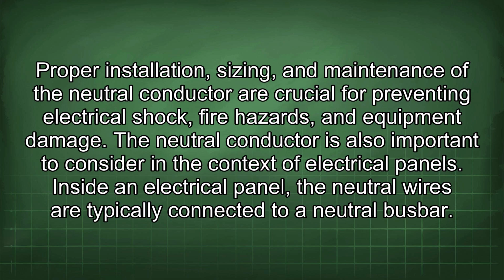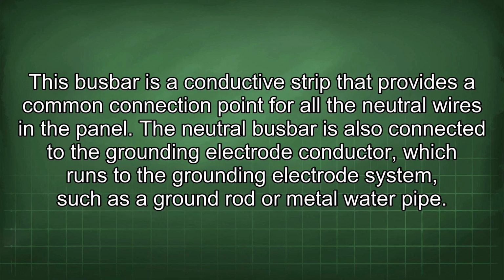The neutral conductor is also important to consider in the context of electrical panels. Inside an electrical panel, the neutral wires are typically connected to a neutral busbar. This busbar is a conductive strip that provides a common connection point for all the neutral wires in the panel. The neutral busbar is also connected to the grounding electrode conductor, which runs to the grounding electrode system, such as a ground rod or metal water pipe.